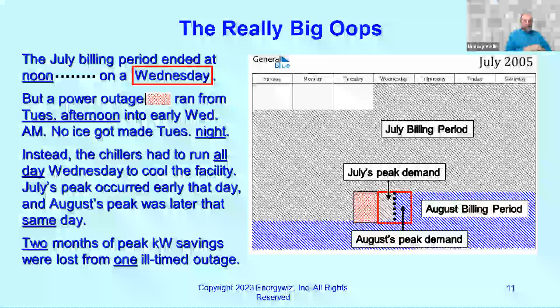The end result was that two months of peak kW savings were lost from one ill-timed outage. Keep in mind we're only trying to control this for about six months out of the year—they lost almost a third of their peak demand savings for that year. That's just a lesson to let you know that we work around the tariff, and to get biblical, the tariff giveth and the tariff taketh away. So understand, when you're running chilled water systems and ice storage systems, you better be sensitive to what can happen if there's a power outage.